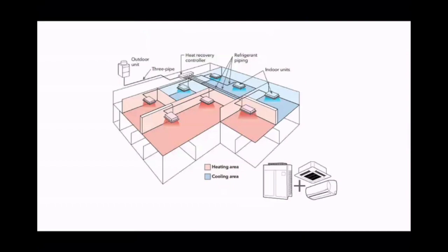Generally they work as what's called a three-pipe system. The way these things work - both the mini split, the multi-split, and the VRF, which are all kind of the same thing but for different size buildings - they'll have pipes. Each of these lines represents a pipe, representing three pipes total: one that has gas in it, one that has liquid refrigerant in it, and one that has suction.